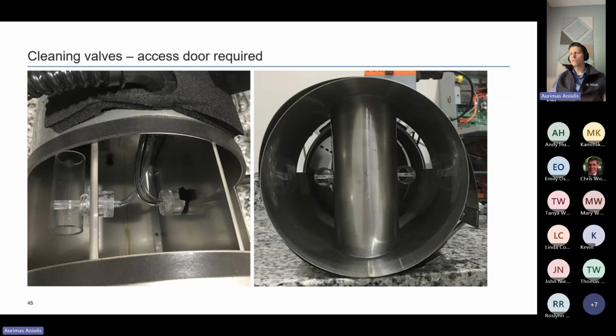That's why some of the valves in the market for critical environments come standard with a clean out door, because they understand that one tissue or enough buildup on their sensors in the airstream is going to render this device useless, is going to throw up a no flow alarm, which is going to trigger a room level controller to go, hey, something's wrong, I'm going to throw the room in alarm. And then you've got a situation where you've got to either evacuate a room or decommission a room and then get somebody else to come in here and try to fix the problem.